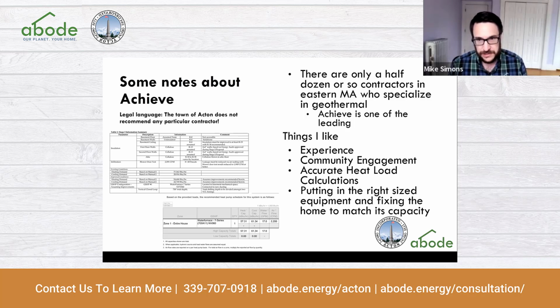The other thing I like as a building scientist: I was reviewing one of his proposals not too long ago, and he flat out designed the system for 54,000 BTUs, even though the home's load was currently 77,000 BTUs. But there's all sorts of things that could be fixed to bring down the building's load—air sealing and insulating the basement were the two big ones pointed out. In my entire time doing this, I've never seen an HVAC proposal from any air source heat pump installer that says, I could be installing 60,000 BTUs worth of equipment.